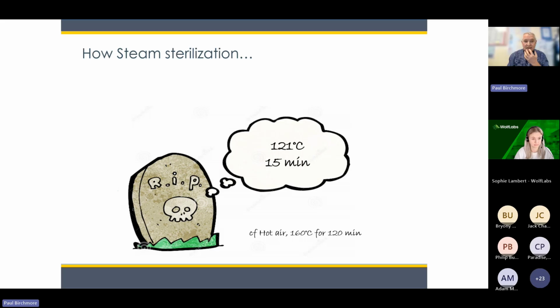Sorry, I should just add, we're going to hear this throughout this PowerPoint. There are a number of little video clips in it that talk about nominal. So if I make it simple, you can do sterilization at a variety of temperatures, but the one you're going to hear constantly is 121 for a duration of 15 minutes. It gets nicknamed the nominal temperature and duration. So just to clarify, that will come up a couple of times on the video. But at that temperature, the steam has released all of that energy back into the cell, thereby destroying it, denaturing it, and you have an effective process.